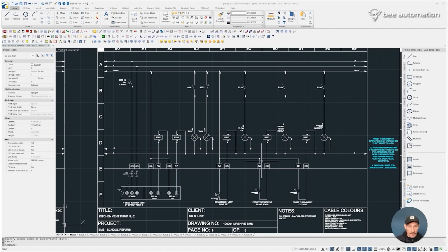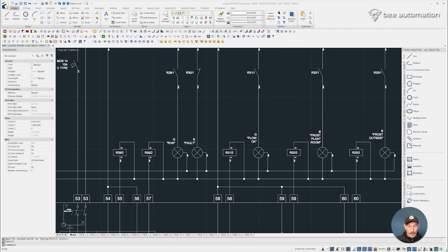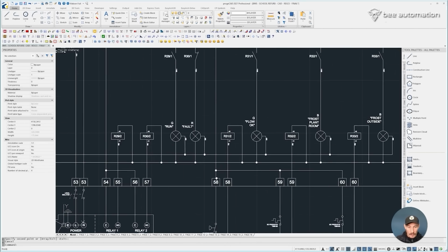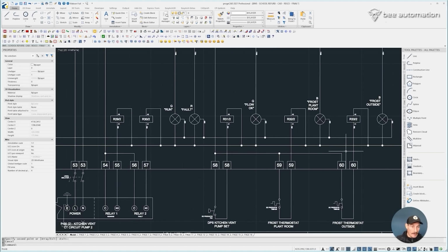Next bit is I'm just removing these cables feeding the differential pressure switches and the thermostats, because what I'm actually doing in the panel is using a little Wago terminal bridge, not a cable, so I'm just removing those. As you can see, I've removed those drops down here, and basically bussed this constant 24 volt supply this way using the Wago bridge connectors.